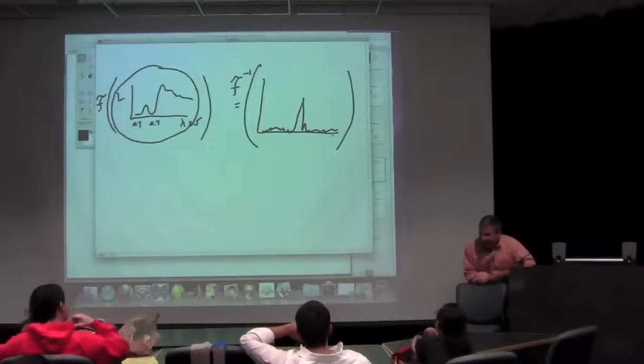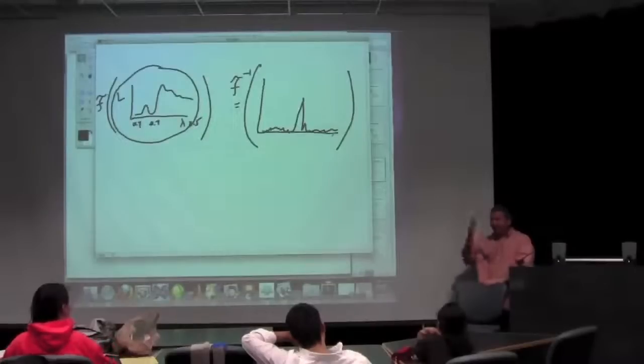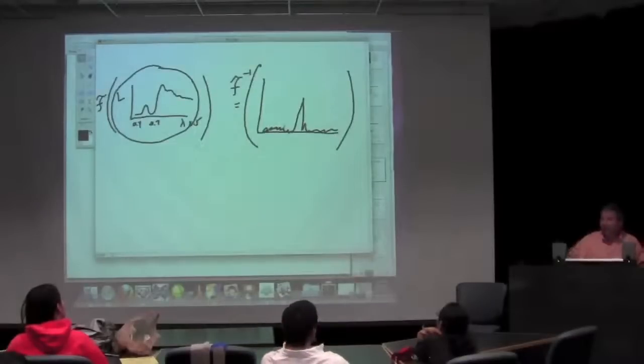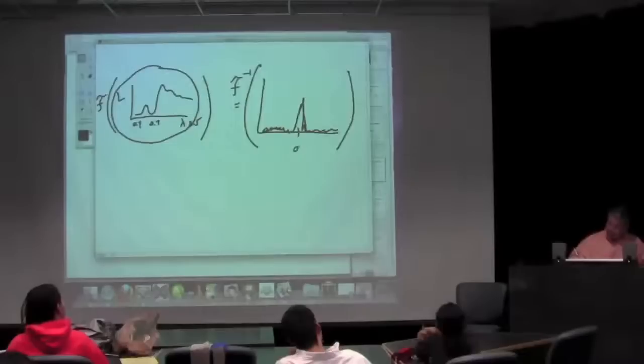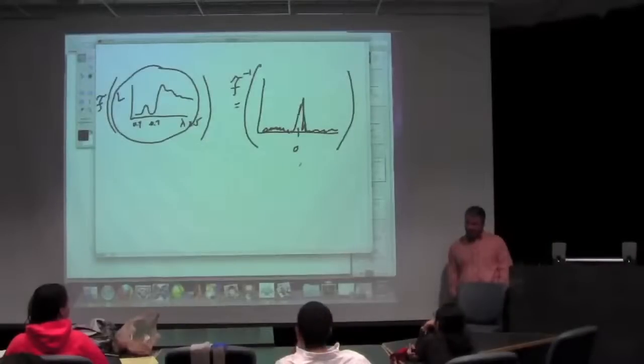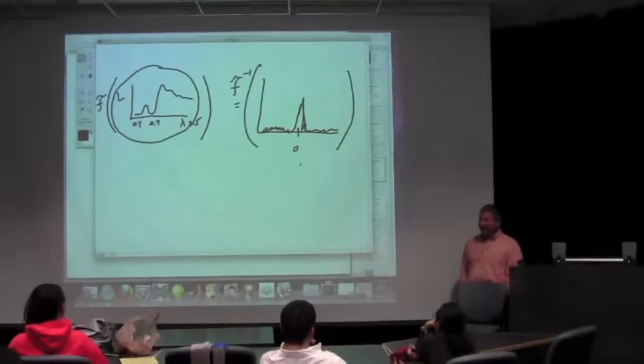Yeah, it's kind of fun to watch this as it scans, right? If you put your eye where the detector is, what do you see? You just see a spot getting brighter and darker. And that brightness and darkness is the fluctuations that you see in your interferogram. When you get towards the center, where everything's in phase, you get a real bright DC component. So this is the zero optical path difference point. So you will go on both sides of that. This is the interferometer, yes.